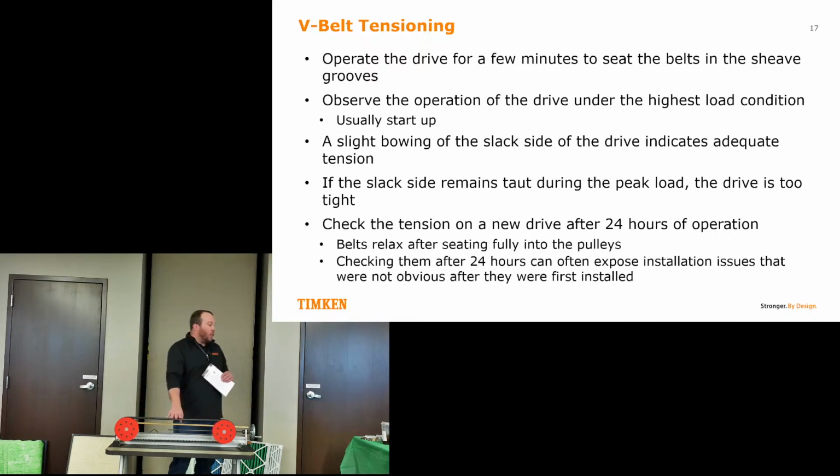So another note on our belts, most tier 1 manufacturers like us have a system in place similar to this, but if you buy any 2 BX68 belts from us, even if they're manufactured a year apart, we guarantee that they will be within the tolerance of matching tolerance. So ASTM, the rubber standards out there, have a matching tolerance guideline for all V-belt manufacturers. And in our manufacturing process, we guarantee that any 2 BX belts will be within that length tolerance so that they will run on a multi-groove sheave and you won't have different lengths in belts, right? Within a tolerance, there might be a very minimal difference, but good enough where you could run your system efficiently and be the same lengths.